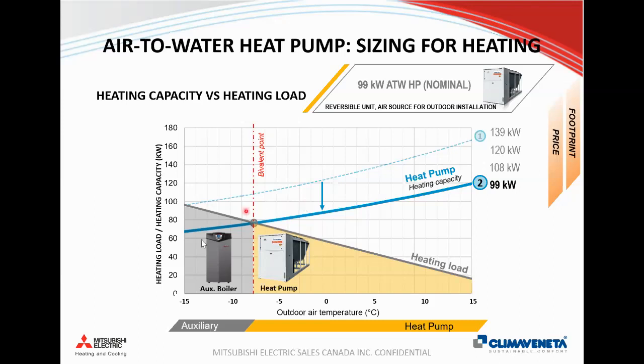If we look on the y-axis here, we have our heating load and our heating capacity. Our heating load for the building is shown with this gray curve. Typically at the coldest temperature, that's where we have our peak load. As it gets warmer, we have less heat losses from the building, so we have less than 100% load. This is an arbitrary curve, for example. It's going to be unique for every building type depending on the insulation and how the central plant's being operated.